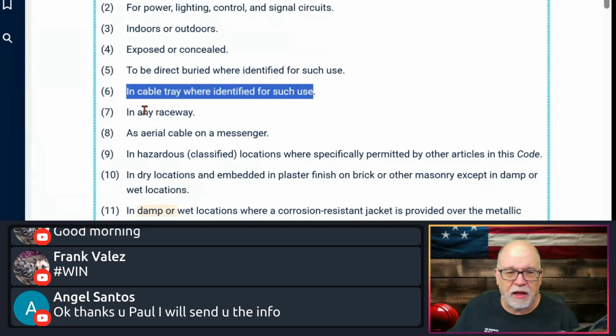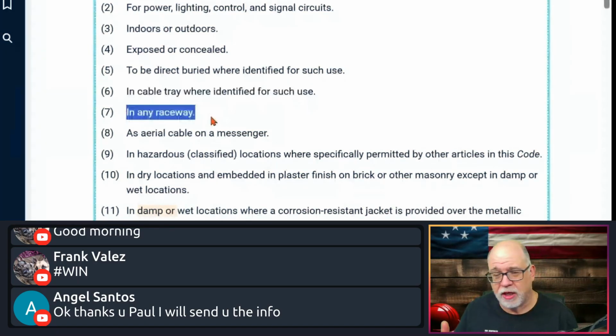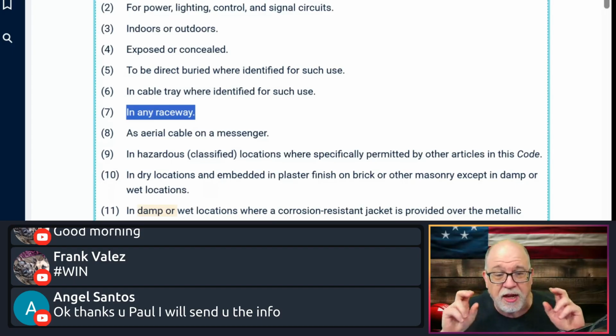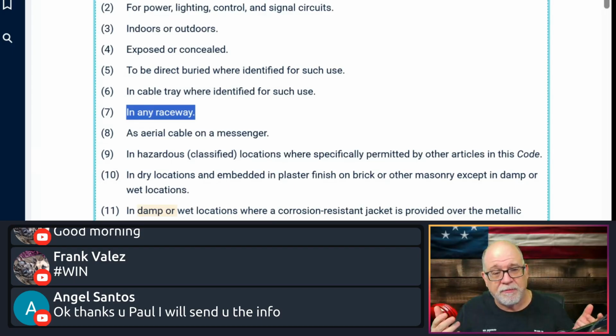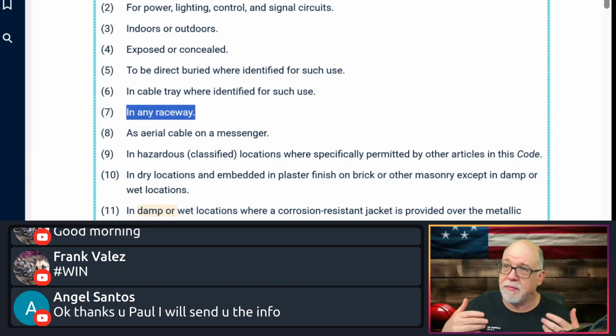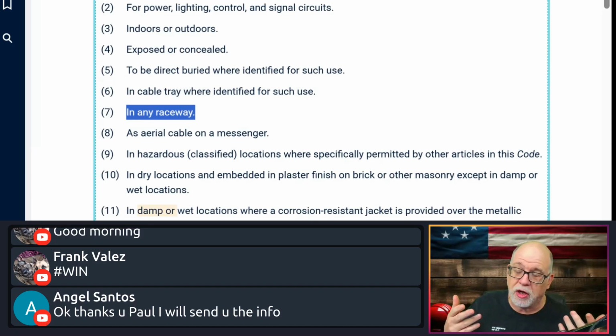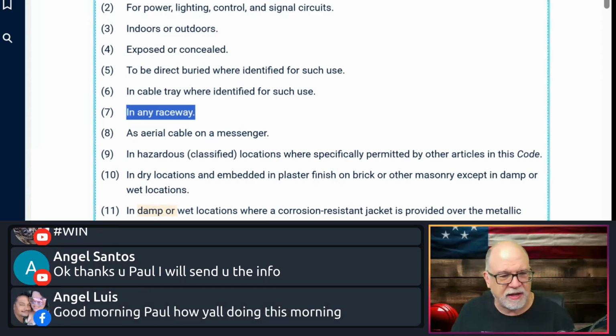In a raceway, a lot of people still question, oh, you can't put NM cable in a raceway. Oh, you can't put MC cable in a raceway. You most certainly can put it in a raceway. Now, you may be doing it for physical damage protection because MC cable, even though it can be aluminum or steel, your choice, is still not rated for severe physical damage. So it may look tough, it may appear so because they say armor, but it is not. You'll see that in a second, right?